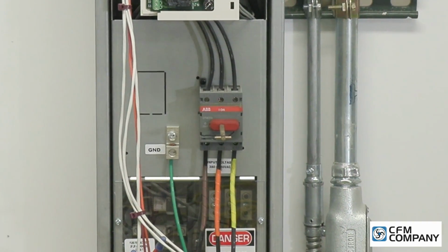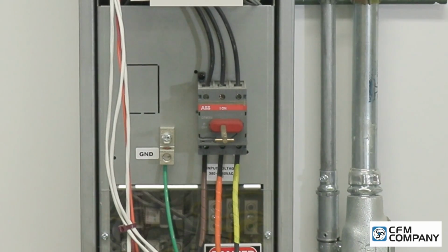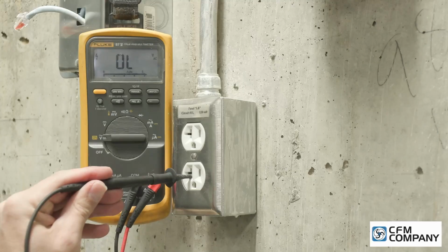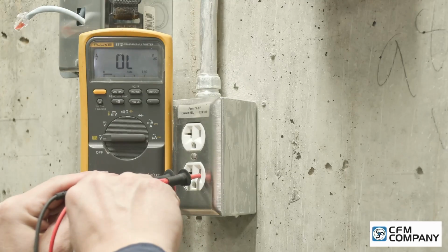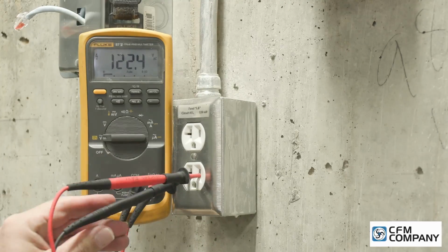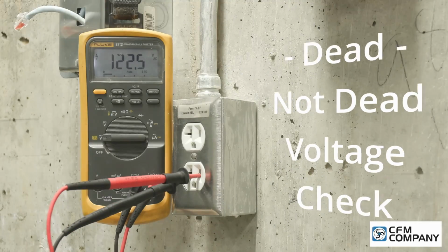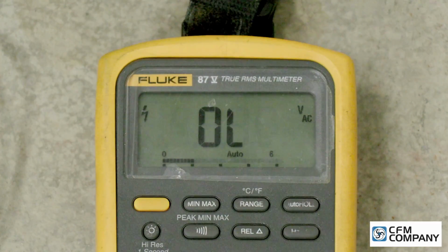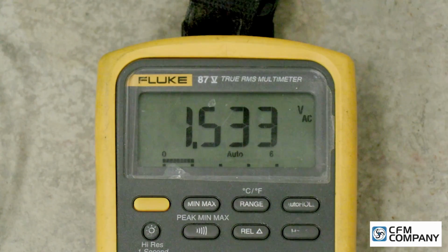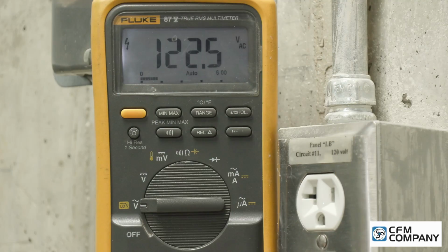Once it has been verified that the line side voltage is dead, verify that the meter is working properly. Using a local power outlet, verify that the meter is not dead. The meter reads 122.4 volts AC. This procedure is known as the dead not dead voltage check. The meter measured the line voltage of the VFD power leads as dead. Then the meter was used to measure the outlet voltage to verify that the meter is not dead. Knowing that the line side voltage is truly dead and the meter is not dead, disassembly of the electronic bypass can start.